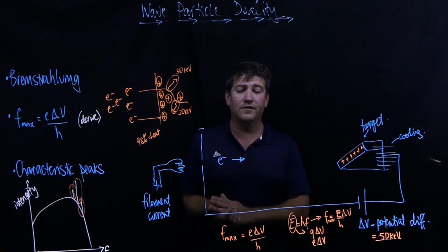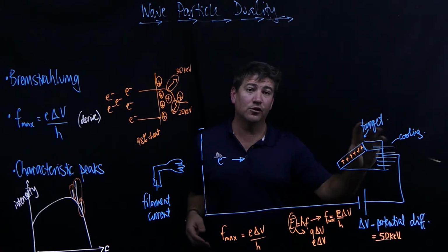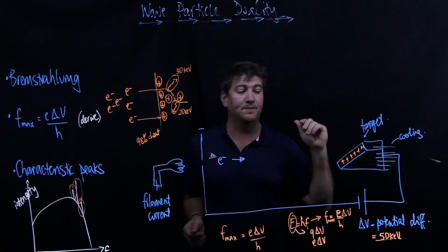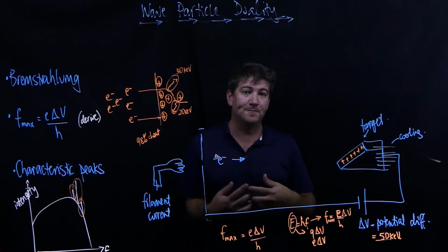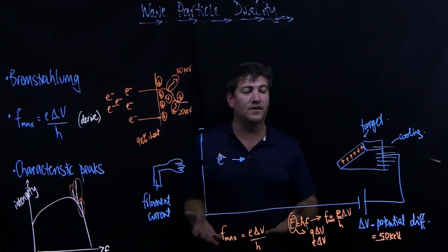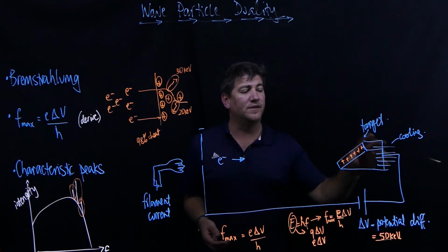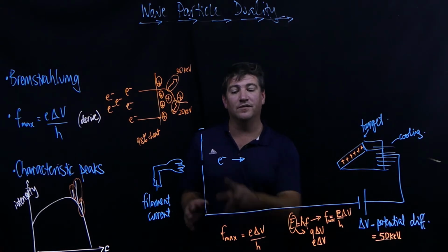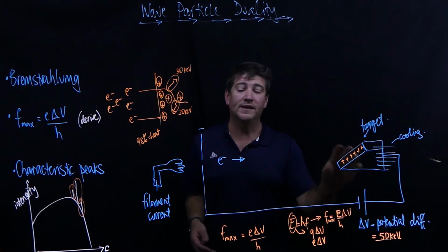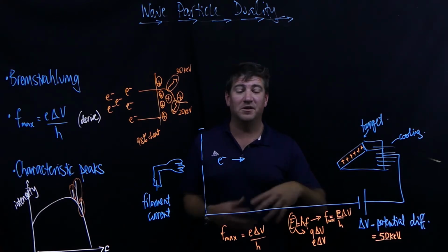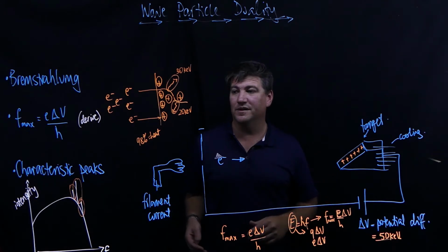Now, because this target material is getting struck by a whole stream of electrons and there is so much heat, we need some way to cool it. A lot of the time it's just fins and so on, so it acts like a heat sink and takes away a lot of heat. Other times you can have them water cooled or oil cooled, but there needs to be some way to cool these things down, because all of these electrons hitting the target will heat it up incredibly, and you can obliterate the target material completely from the surface, and then it's flat out useless.